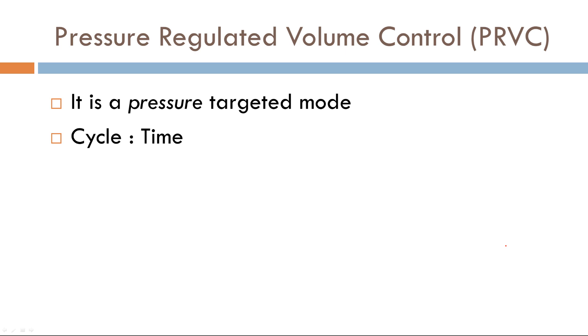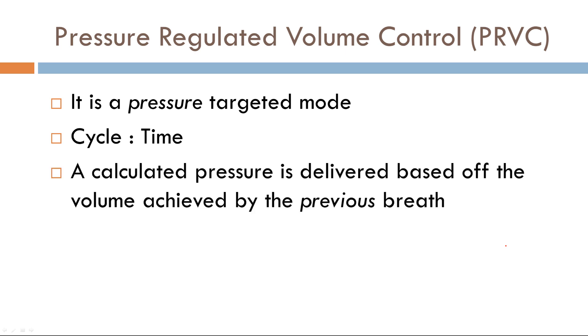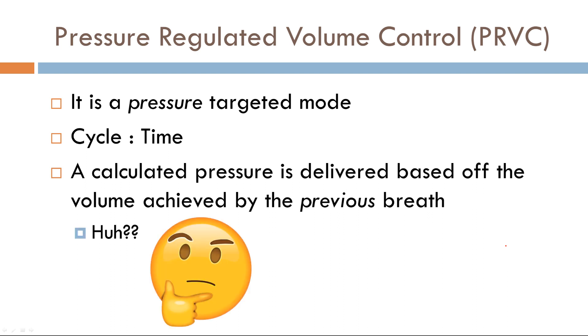So the key difference is, for PRVC, a calculated pressure is delivered based off the volumes achieved by the previous breath. Now I'm sure some of you are a little bit confused by this, but not to worry. In the subsequent slides, I'll be showing images of PRVC and keep on coming back to this statement. So with time, the statement will hopefully make a little bit more sense.